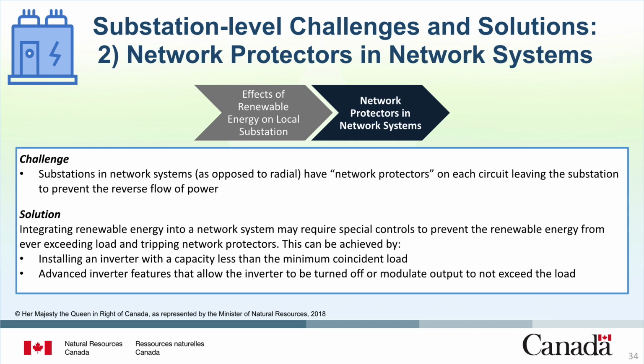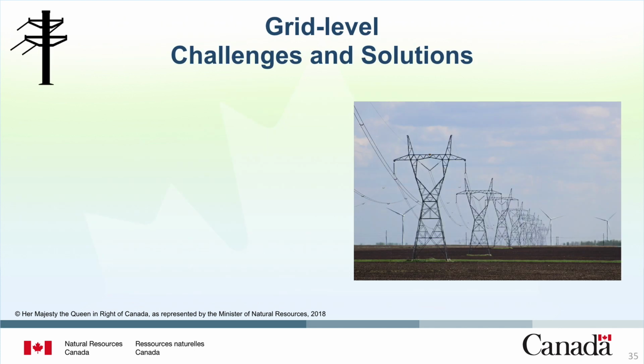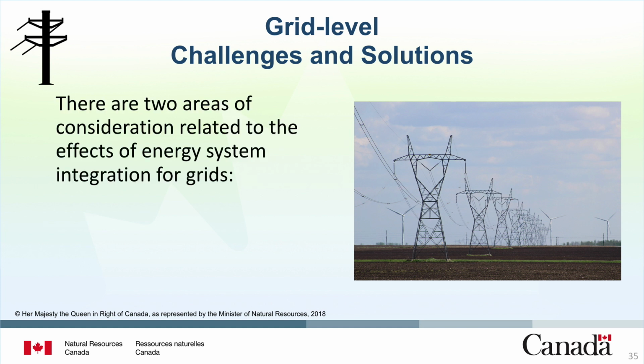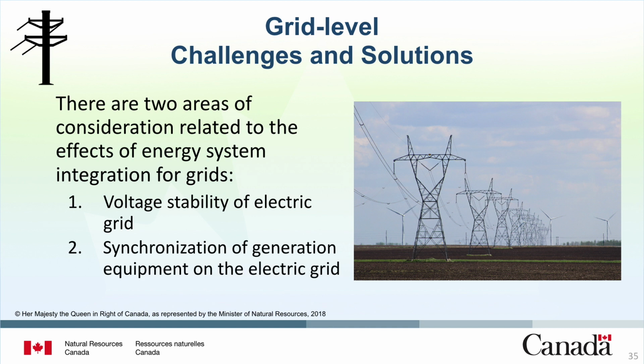This can be achieved most simply by installing an inverter with a capacity less than the minimum coincident load, but may also be achieved with advanced inverter features that allow the inverter to be turned off or modulate its output not to exceed the load. Now we move from discussing challenges and solutions at the substation level to the grid level. There are two areas of consideration related to the effects of energy system integration for grids: 1. Voltage stability of the electric grid, and 2. Synchronization of generation equipment on the electric grid.